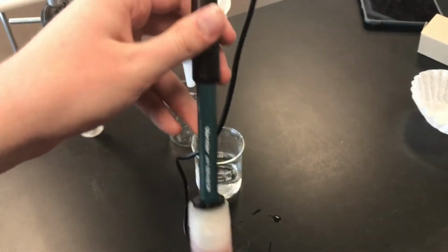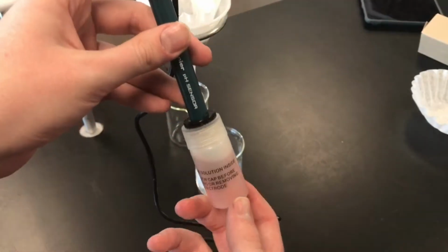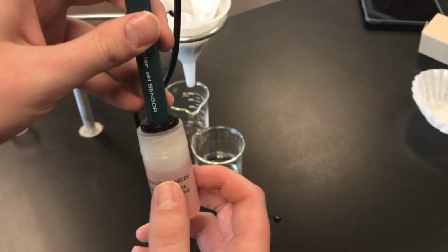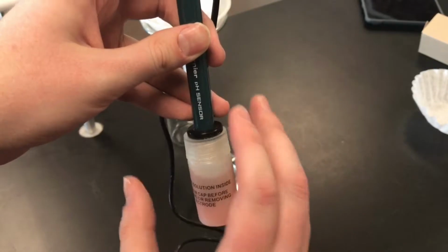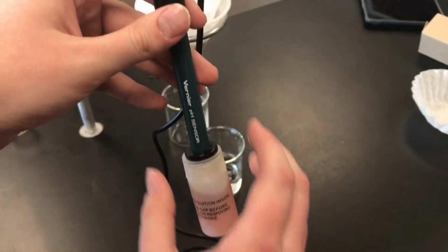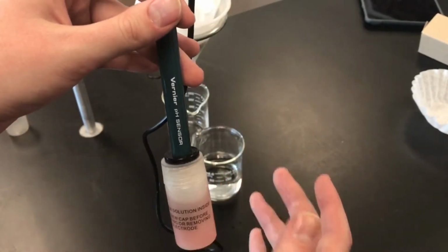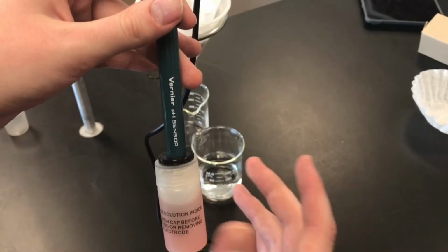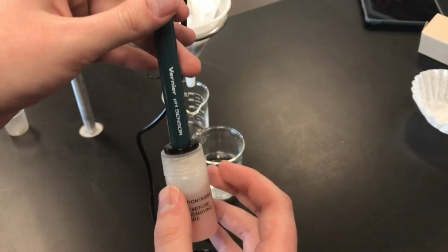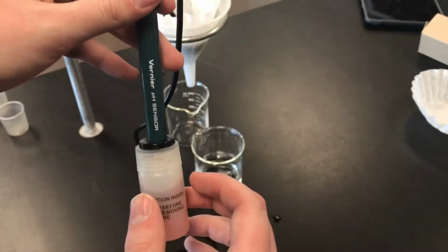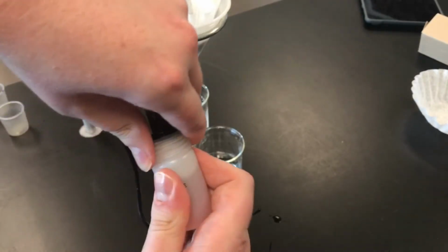The best way to take off the buffer solution here, and it's really important that you don't spill or mess around with this buffer solution. This is what's going to keep the pH meter calibrated and also safe from potentially breaking if this solution is spilled or if the pH sensor is left out too long.